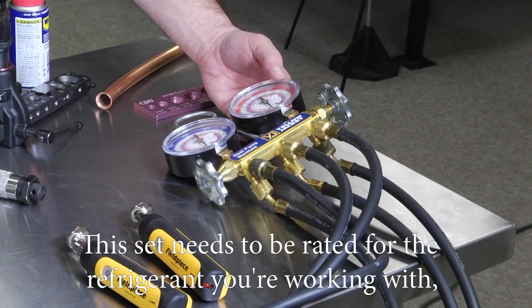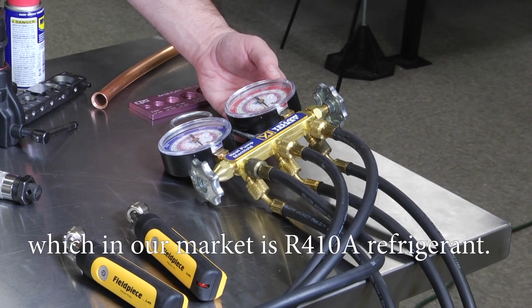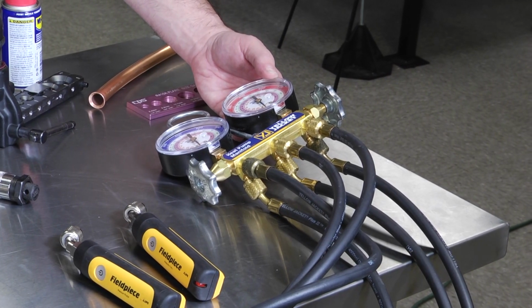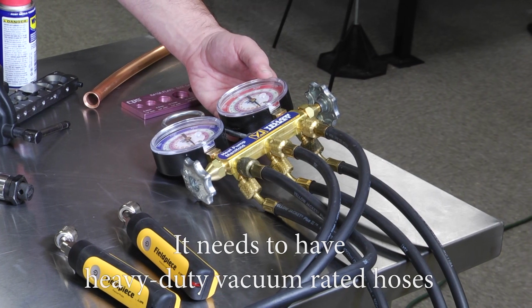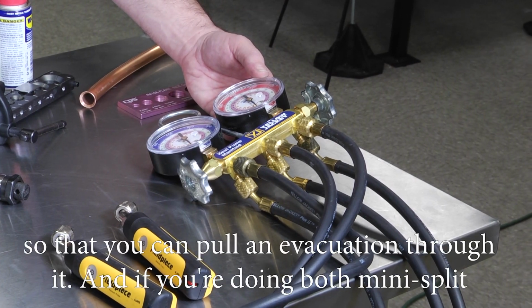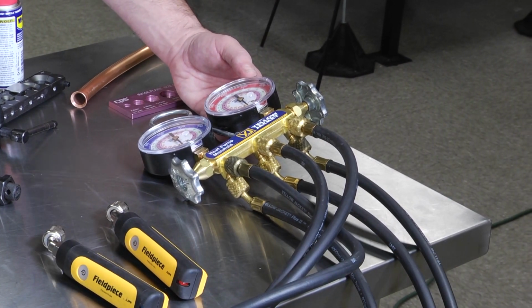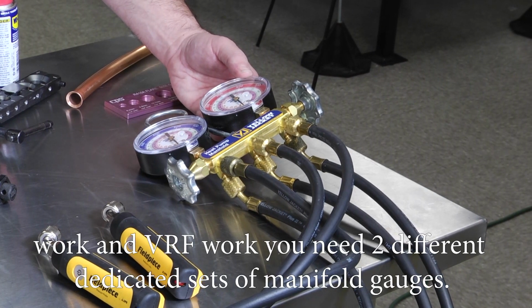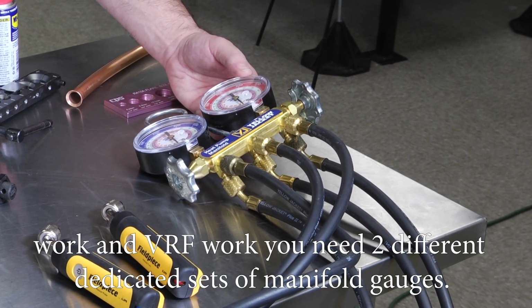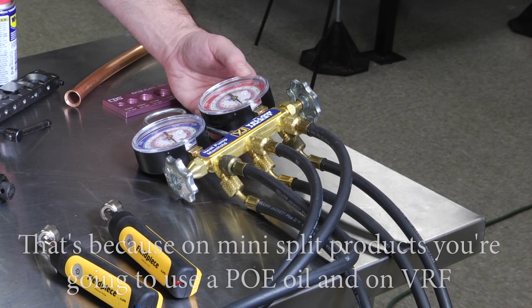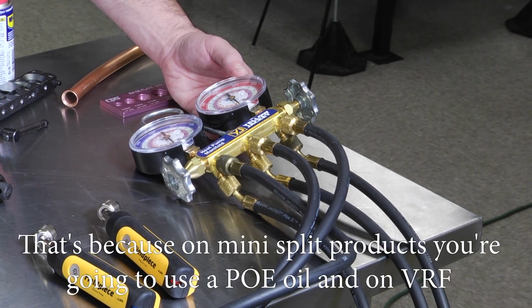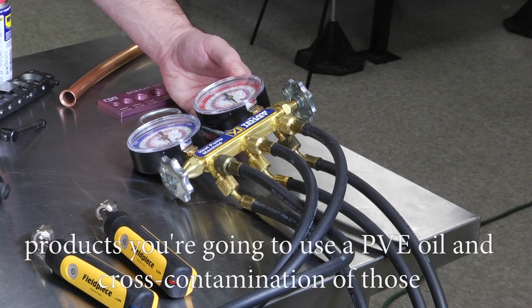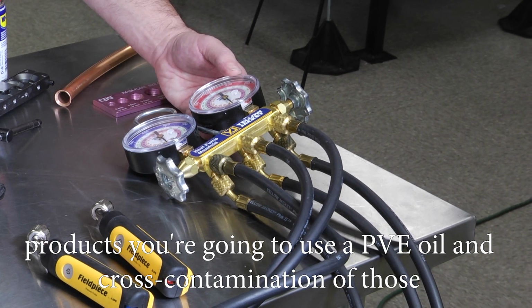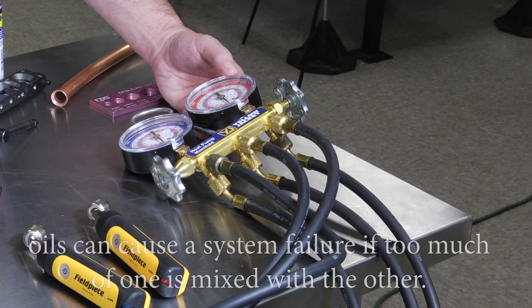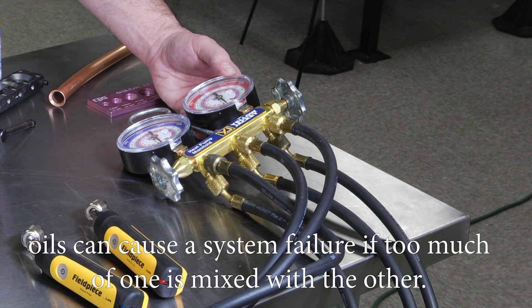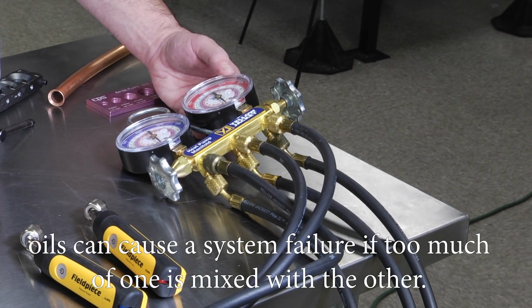This set needs to be rated for the refrigerant you're working with, which in our market is R410A refrigerant. It needs to have heavy-duty vacuum-rated hoses so you can pull an evacuation through it. And if you're doing both mini split work and VRF work, you really need two different dedicated sets of manifold gauges. That's because on mini split products, you're going to use a POE oil, and on VRF products, you're going to use a PVE oil. And cross-contamination of those oils can cause a system failure if too much of one is mixed with the other.